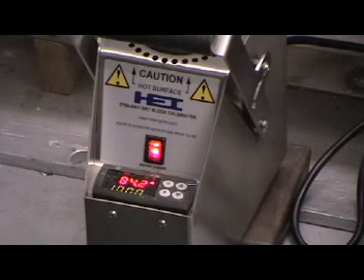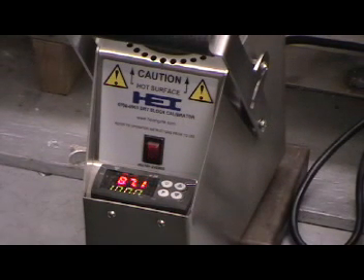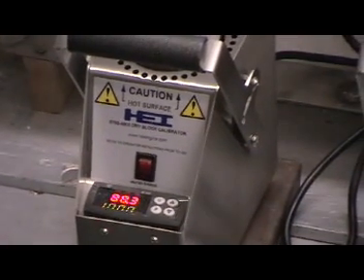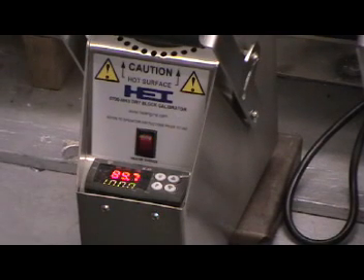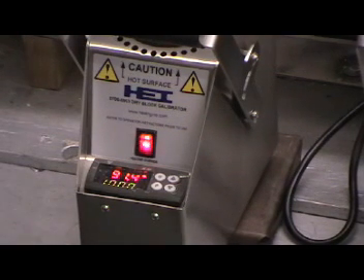The switch labelled manual override, which you can see flashing under the HEI label, can be used in a variety of ways. This is useful for setting switches either rising or falling, and saves resetting the set point each time. We have some examples in our instructions of how this can be used. In general, the idea is to help speed up the operation of calibration on site.